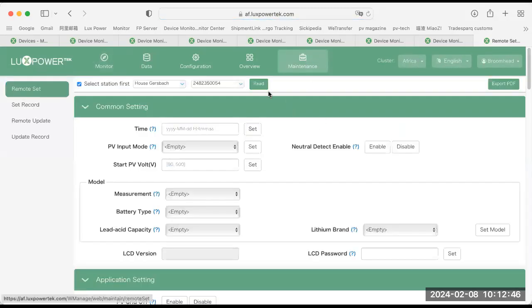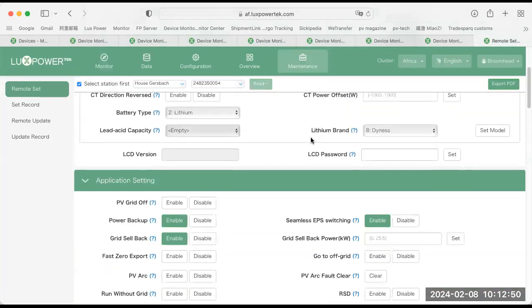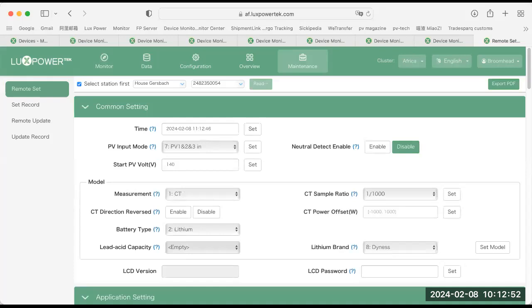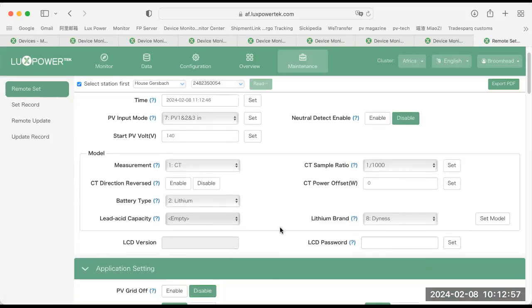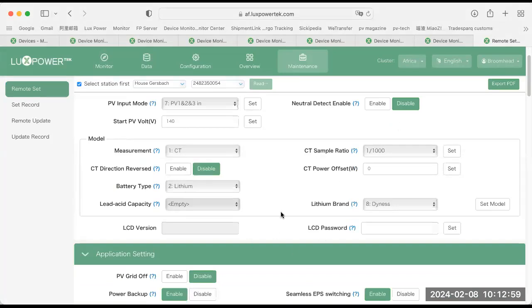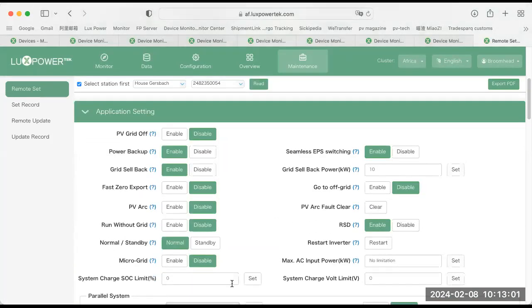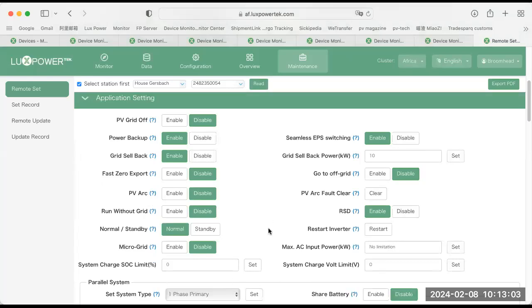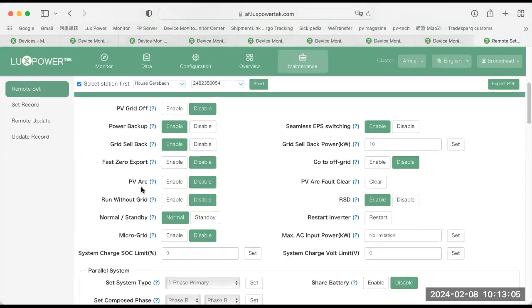All right, so here we've got a 10 and a 12K viewing page. So we're just going to do the read, and you can see that immediately the settings page is different to the 5, right? But a lot of them are the same, especially this particular section here. The nice thing with the 10 and the 12 is that we've got the PV arc fault, but I'm going to check with Joe if this feature is available to the EU machines or it's still only for the US machines. PV arc and fault clear.